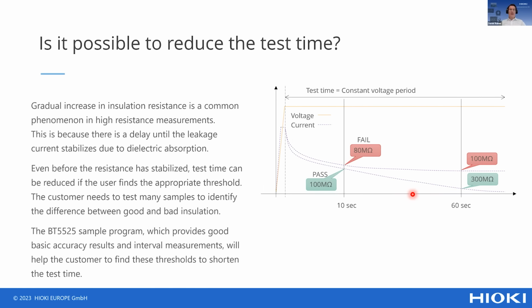Yeah, but in any case, it would make sense maybe to reach out to us so that we can go a little bit closer into your application to understand what is your purpose of the measurement, and then we can decide which product makes most sense for you. Because the BT3560 series is typically already a test not for the battery cell anymore, but in most cases, it's already the pack or the module you are testing. And you simply want to have maybe an inspection or end of line test to understand the internal resistance value or the voltage level of your battery cell, pack or module.